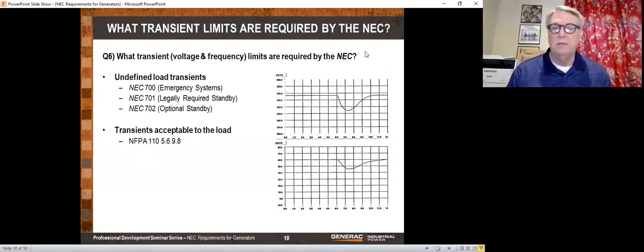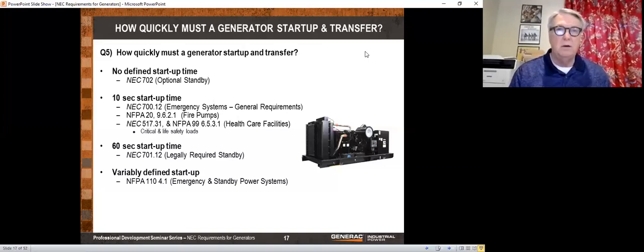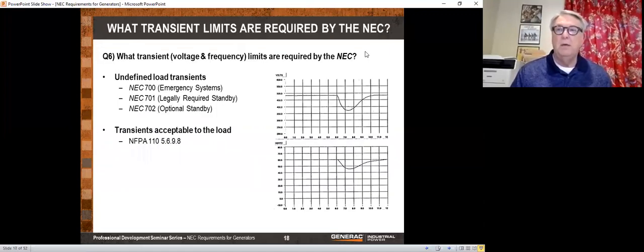By the way, that's Generac. Don't expect other manufacturers to be able to do that. And if you're speccing a generator and you're speccing a 500 kilowatt natural gas generator, don't just anticipate that it's going to be okay. You better put that in your spec, that it has to start up in 10 seconds. Otherwise, you may be unhappy with the result.